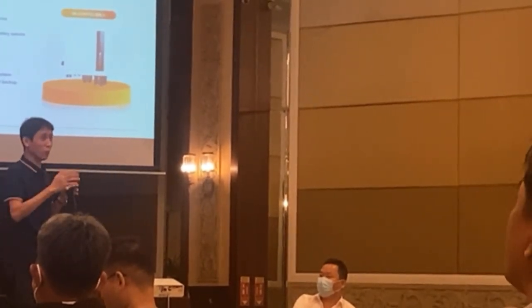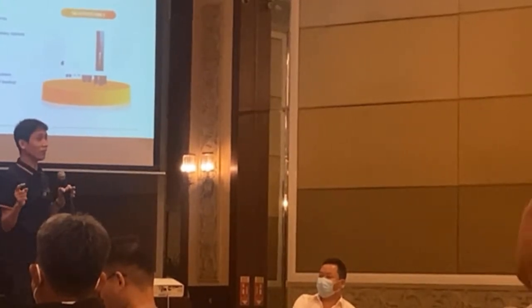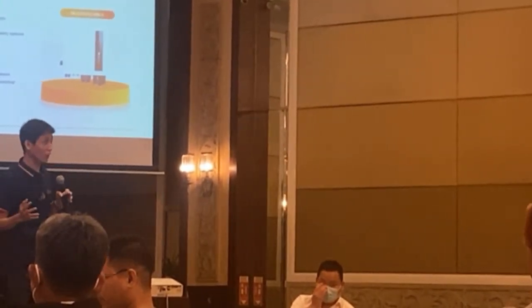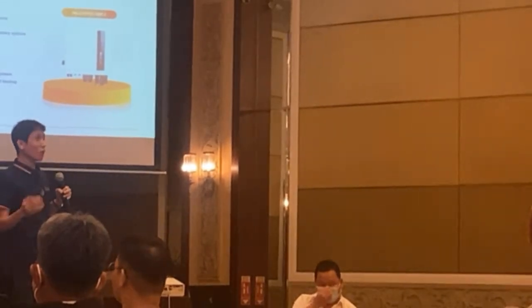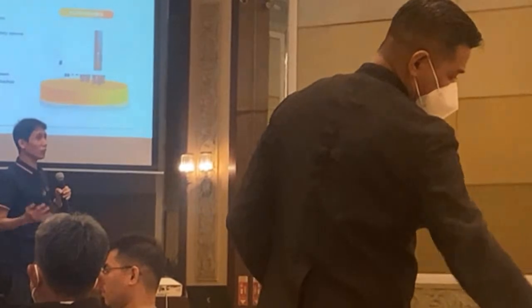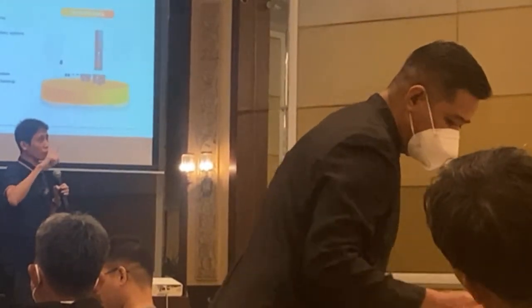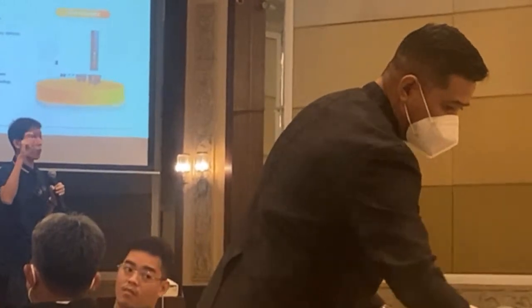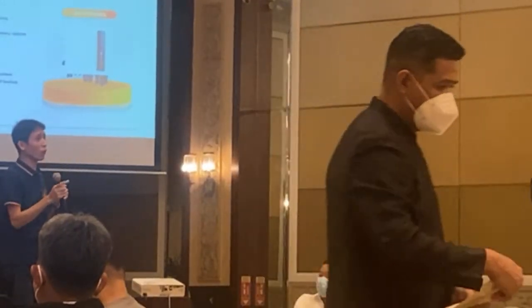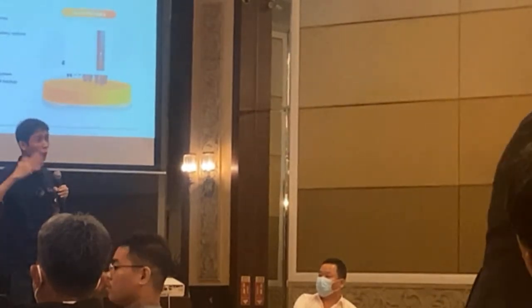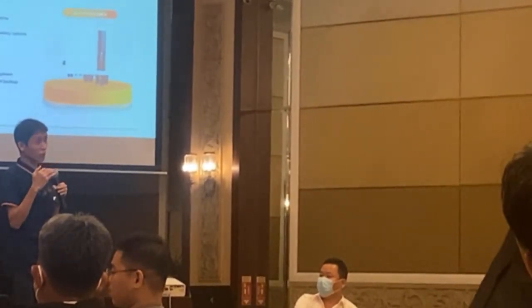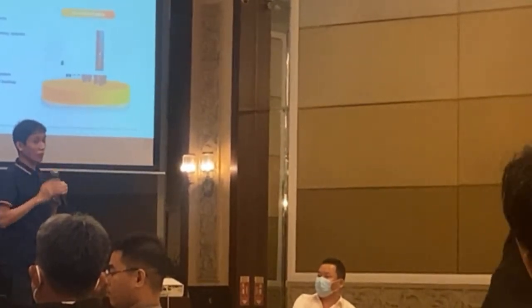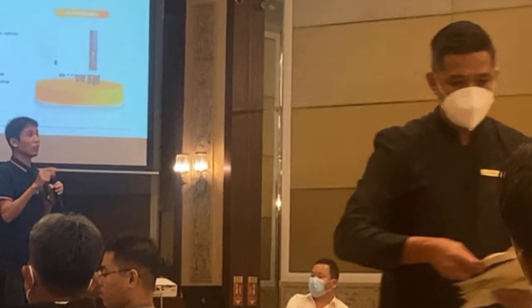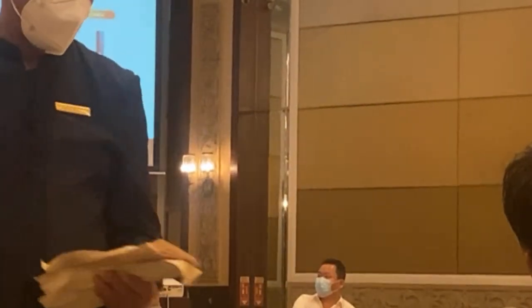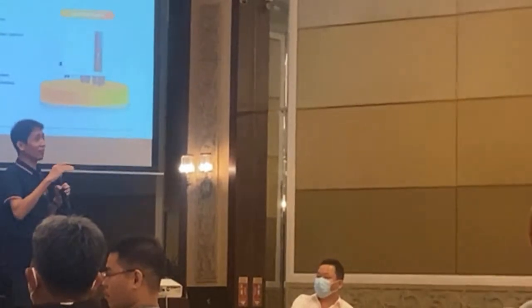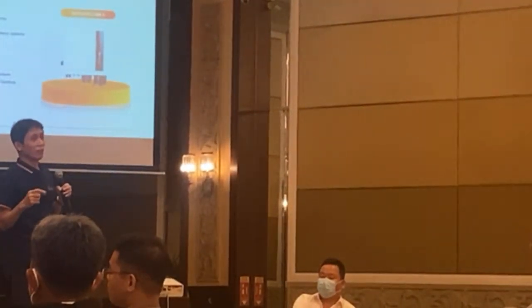If you don't want to use the APM and you're waiting for your limiter, all you can do is throttle your inverter. How do we do that? Backflow. Just tell the inverter if my peak is only 10 kilowatt, then set your backflow to just 10 kilowatt, so that it will not go beyond. It's capping on the inverter side so it won't exceed, because you instruct how the inverter works.